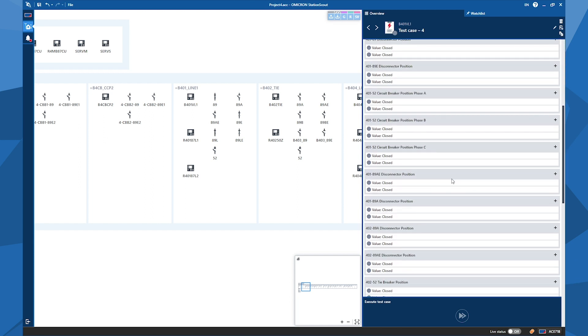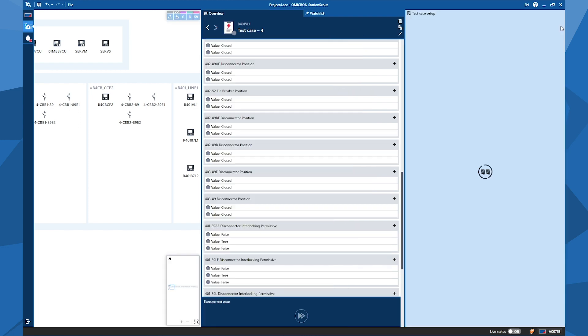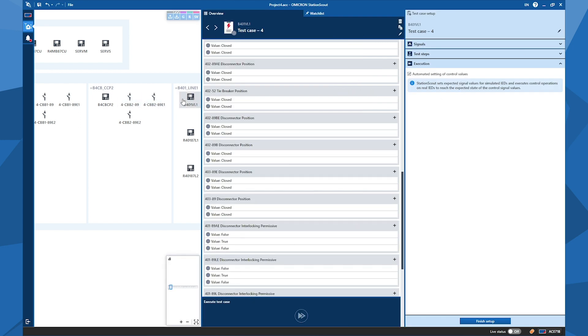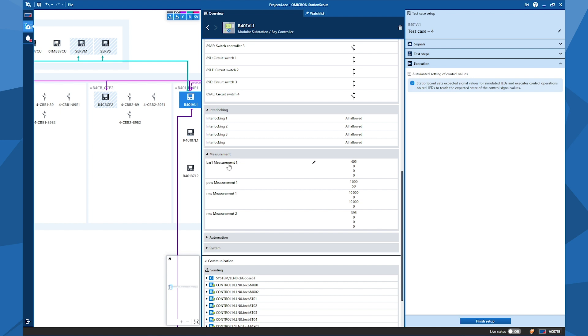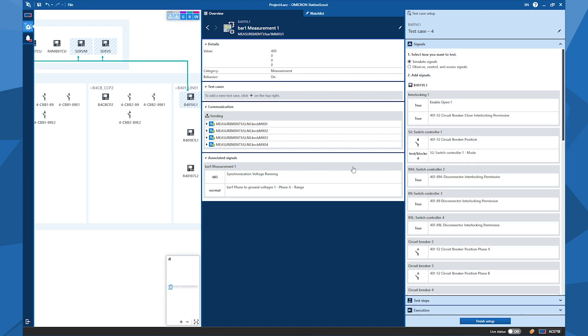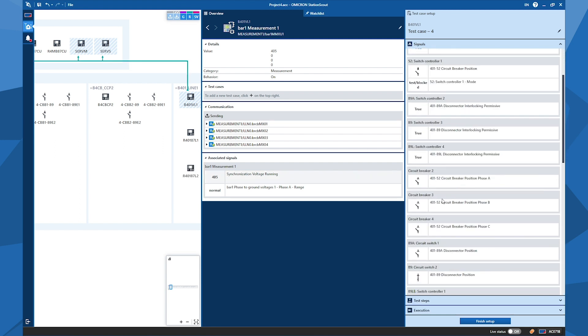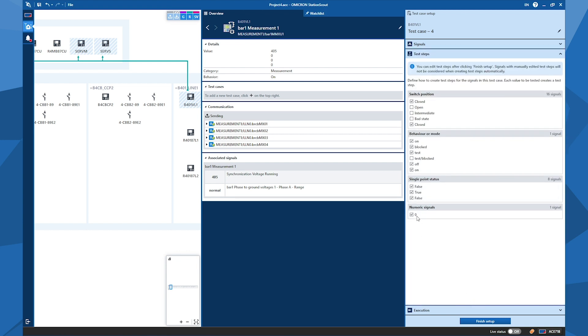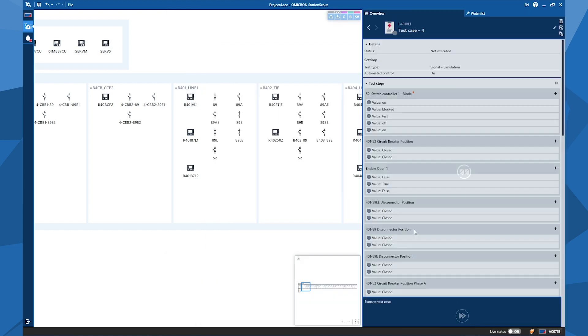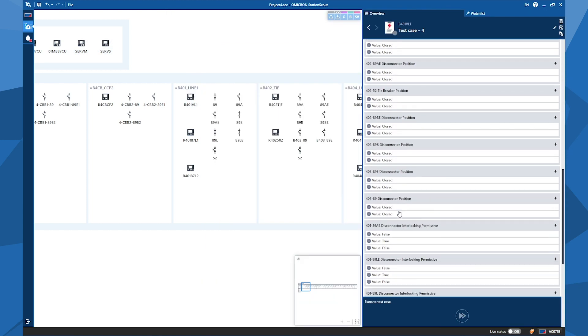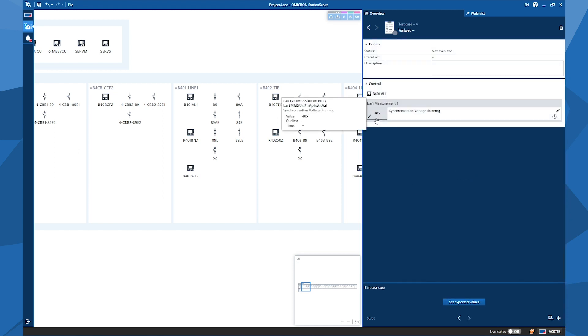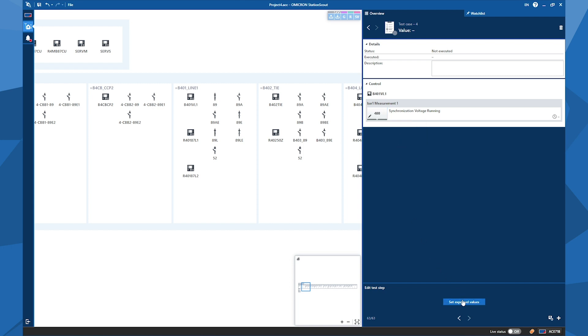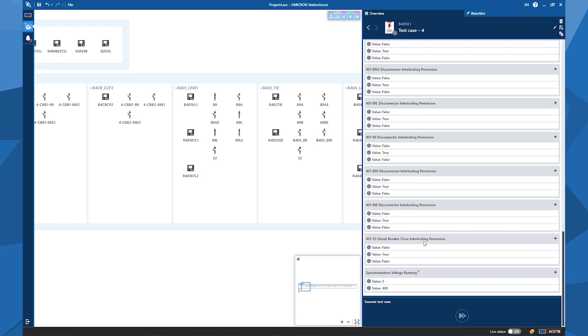So for the analog values, if you want to test, we can also add some analog value. So go back to the measurements of the IED again. So select an analog value like synchronization voltage running. So I can add this also to test step. You see that it appears here. And finish the setup again, but before that, you will see that numeric signals also appeared. We don't offer any numeric signals, but if you want to add some desired values, you can also do that via clicking on the plus icon and setting some different values, like 400 kV, and again clicking on the set expected values. Now if I go back to test case setup and scroll down all the way, then you will see that value with 400 volts or kilovolts have been added.